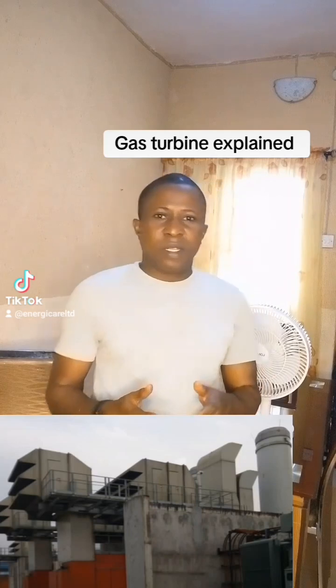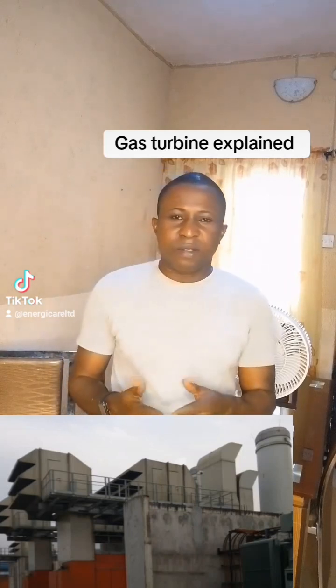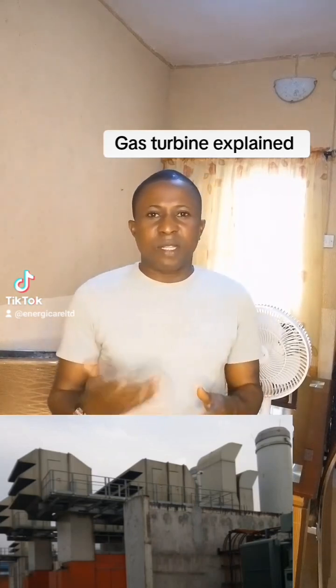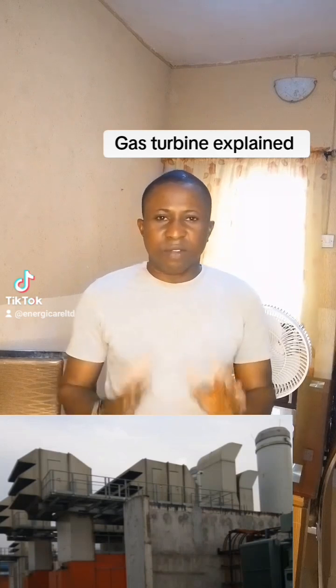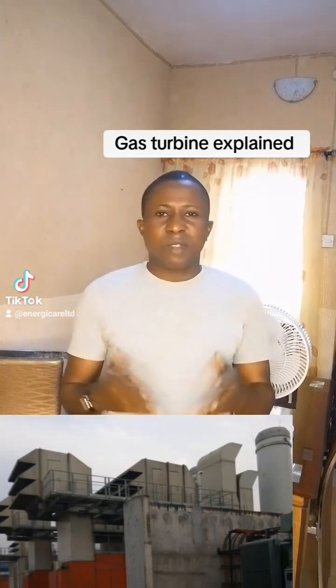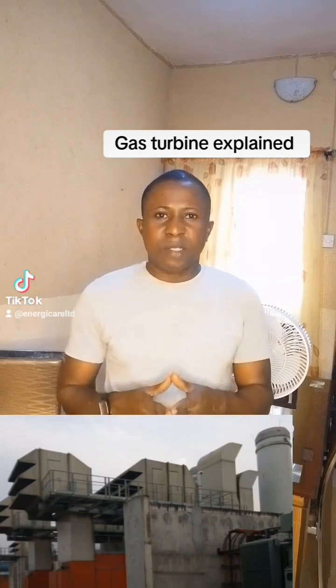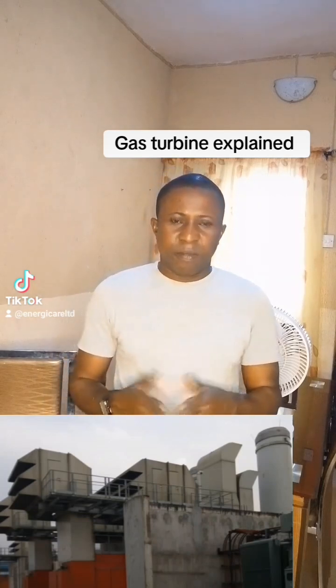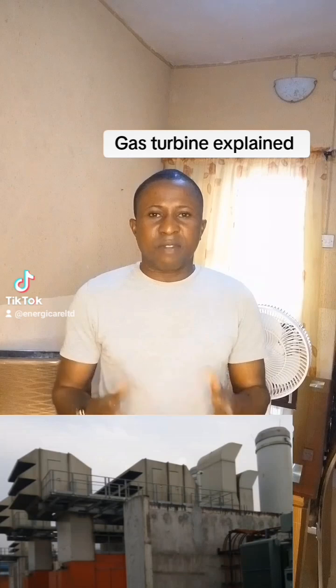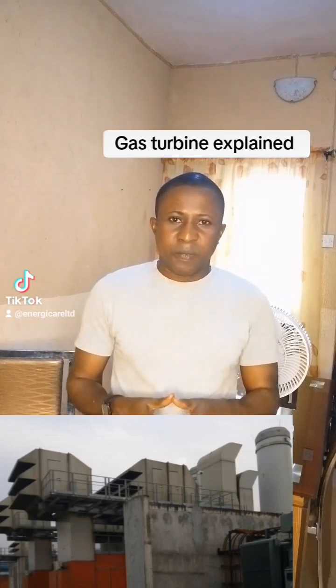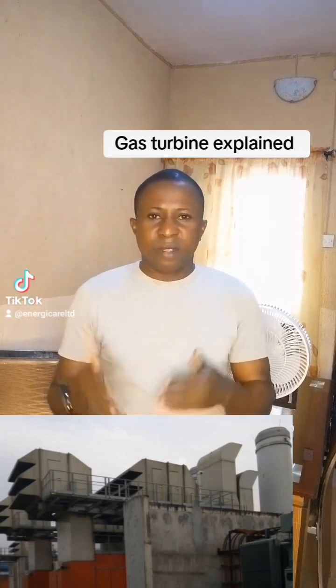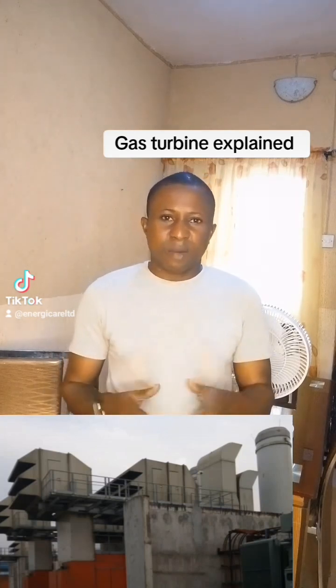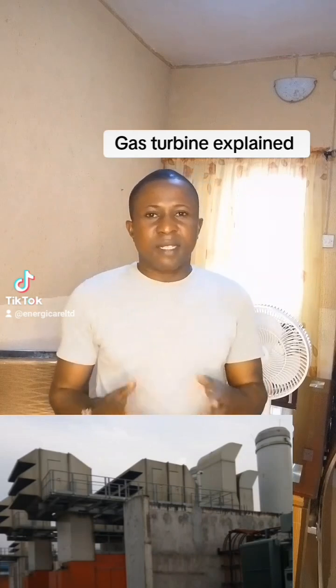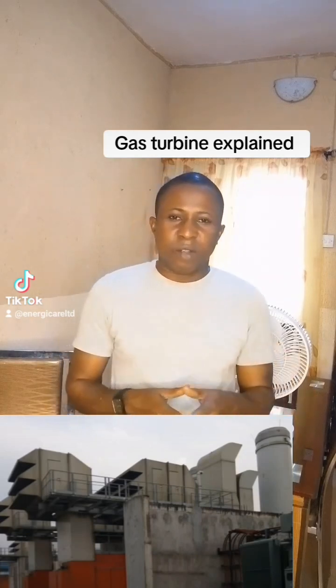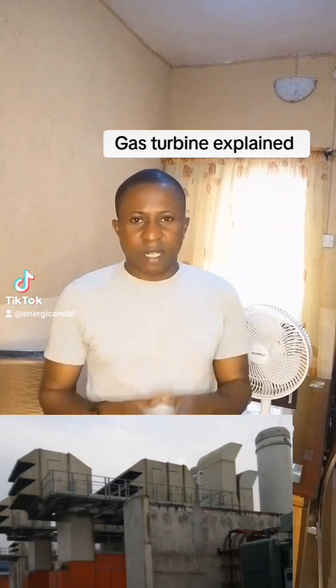If particles and dust are allowed to go to the compressor, it's going to foul the compressor, and this will increase the rate of compressor water washing. Because when the compressor is being fouled, the output of the turbine will drop. So, to reduce the rate of compressor water washing, which is not an easy task, you need to make sure that the air is well filtered.